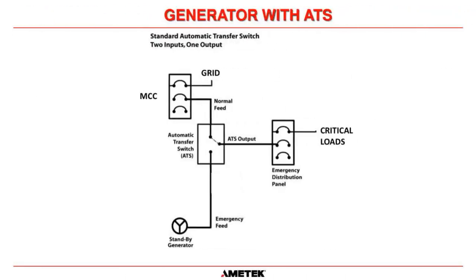So first of all, here is the most basic diesel generator backup that you can have that doesn't use a UPS, and many emergency lighting systems use a system very similar to this. At the top, you have AC power coming in from the grid. That goes into an MCC, and then the normal feed goes down into this automatic transfer switch. You can see in normal operation, the contact goes directly out to the automatic transfer switch's output, and then to an emergency distribution panel. And that's where you'll find your critical loads.